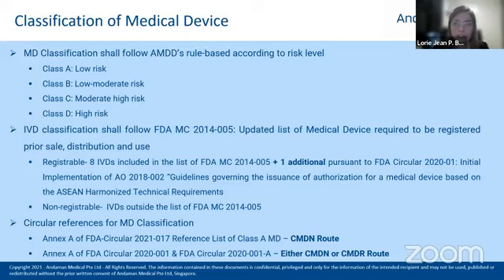For IVD classification, currently it's either registrable or non-registrable. For registrable IVDs, we follow the FDA Memorandum Circular 2014-005, which is the updated list of medical devices required to be registered prior to sale, distribution, and use. In the Memorandum Circular 2014-005, there are only 8 IVDs required to be registered, but blood collection tube was added on this list pursuant to FDA Circular 2020-01, which is the initial implementation of the AO, which is the guidelines governing the issuance of authorization of a medical device based on ASEAN harmonized technical requirements. So now the list of IVD will be shown to you later.